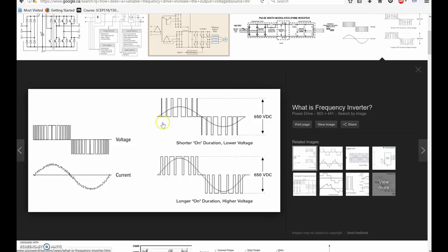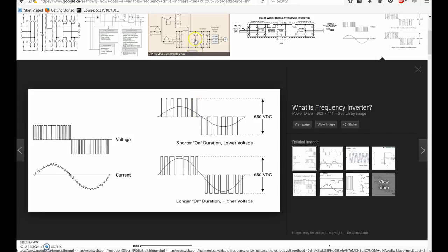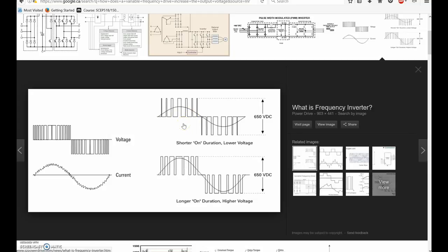By changing the frequency, you change the output sine wave to the motor, which changes the speed of the spinning magnetic field. The DC bus voltage stays the same, but to get higher voltage output at the same frequency, the pulse width modulation timing — how long the square waves are on — is increased. Comparing two sine waves, the frequency is identical but one has larger voltage output because the transistors were on for longer for each pulse.